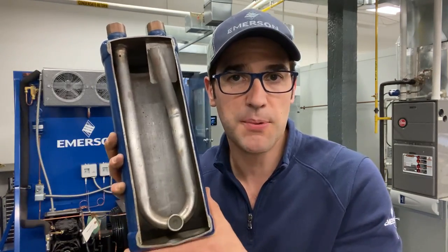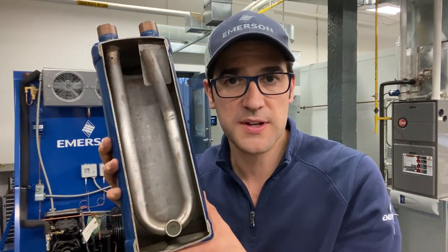Anytime you lose a little bit of control and the evaporator doesn't boil off, this accumulator will catch it and protect against flood back. It won't protect against flooded starts or other issues within the system, but it will protect against flood back.